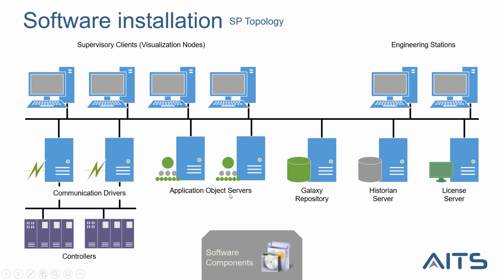Regarding the application object server, we always recommend, in case of a non-telemetry server, to have the communication driver and the application object server installed on the same PC. Let the objects on the application object server read locally and communicate locally with its driver before reaching the controller.